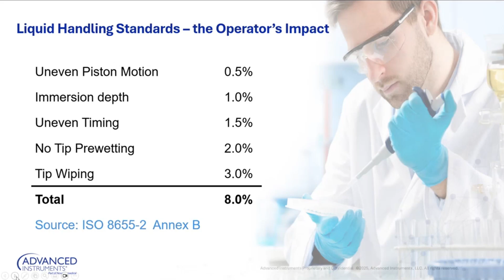And ISO is pretty well documented about the impact of the operator's technique. So depending on how your operators are using pipettes, they could contribute up to 8% influence on volumes. So if you add that to the 3.5% influence from the environment, you're now up to an 11.5% influence on your volume. Right. And so you can see how the error compounds very quickly and why this stuff is so important when it comes to the maintenance and the structure of your liquid volume verification in-house.